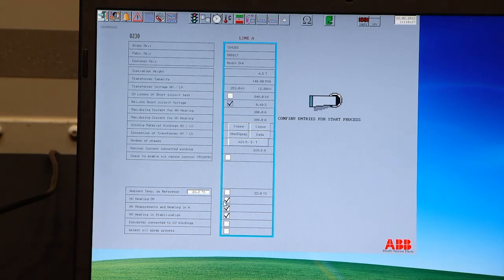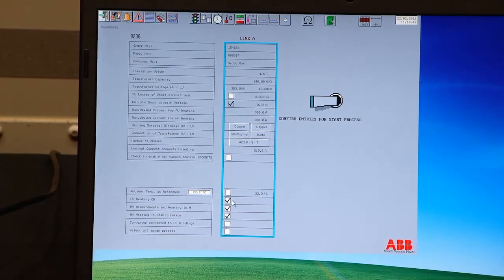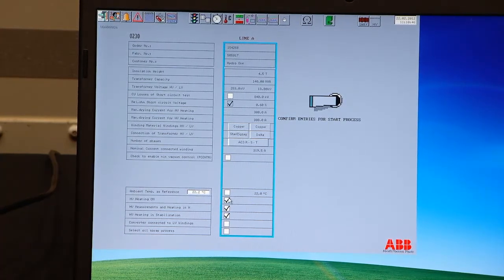Okay, the next option you will have is to perform a high voltage measurement, high voltage heating. That is to heat only one side of the transformer, and that is the winding you're connected to, which is a high voltage winding. I'm discussing in singular, but of course you're talking about all three windings. Then you will have two other high voltage measurement options, and that is for high voltage measurement and heating in the heating phase. And you have the high voltage heating in stabilization phase. Check both of them, and then you have the option to uncheck it later if you need to.